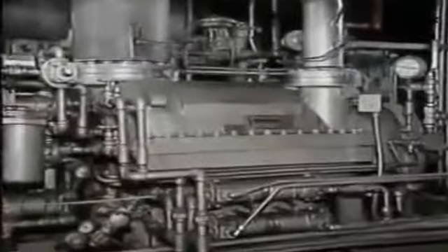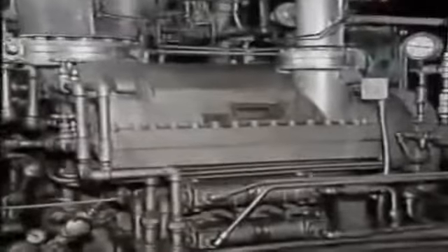As a general rule, it's important not to exceed the ramp rate while a compressor is being brought up to speed. However, in many centrifugal and axial compressors, certain rotational speeds, called critical speeds, cause severe vibration. This vibration is caused by the physical characteristics of the compressor's rotating parts. The vibration can be severe enough to seriously damage a compressor. Critical speeds are often identified in a compressor's operating procedures, and they occur when the compressor is at less than full operating speed. When a critical speed is reached, the ramp rate is usually increased to pass through the critical speed as quickly as possible.